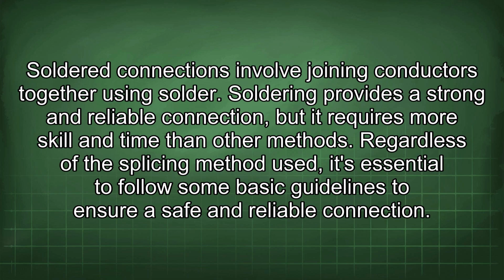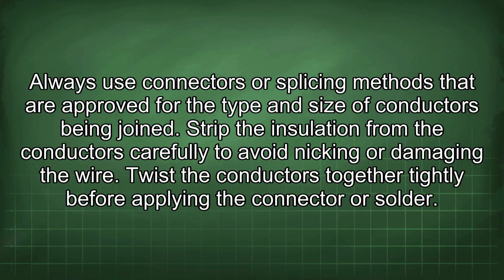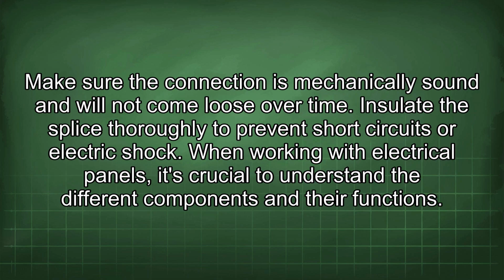Regardless of the splicing method used, it's essential to follow some basic guidelines to ensure a safe and reliable connection. Always use connectors or splicing methods that are approved for the type and size of conductors being joined. Strip the insulation from the conductors carefully to avoid nicking or damaging the wire. Twist the conductors together tightly before applying the connector or solder. Make sure the connection is mechanically sound and will not come loose over time. Insulate the splice thoroughly to prevent short circuits or electric shock.